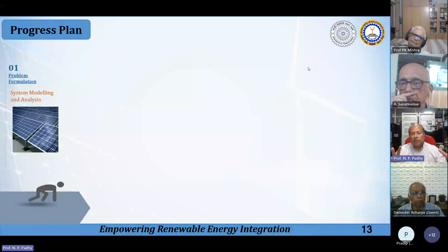So we do have both the challenges. All the time, the PV energy is being consumed by the campus itself. But during summer, we see a bit of voltage issues because of extremely low loading conditions in the laboratories as well as in the hostel campuses. So we have modeled the whole IIT Roorkee campus, which was not in order. The line resistance, line reactances, substation data, nothing was physically available. So we tried to gather it.